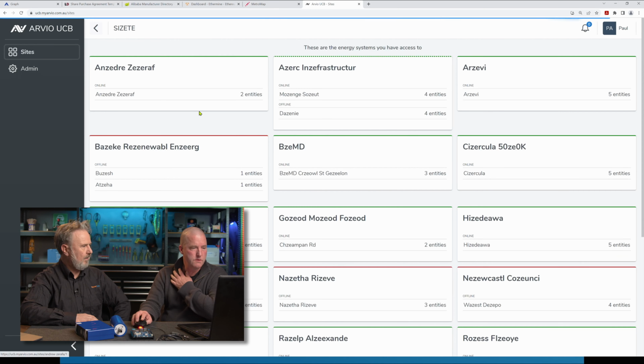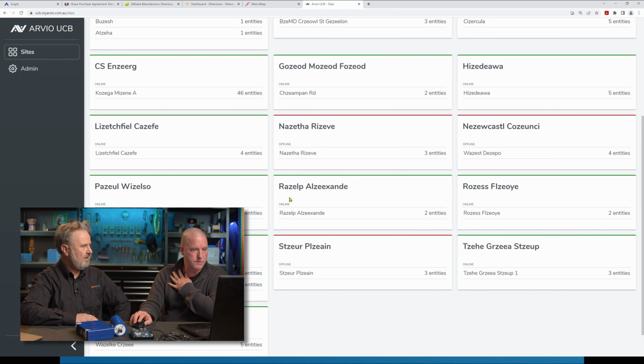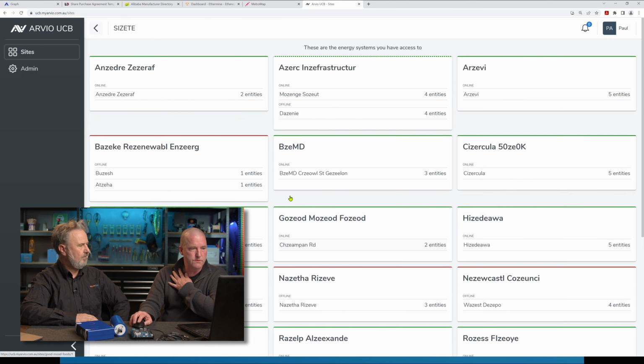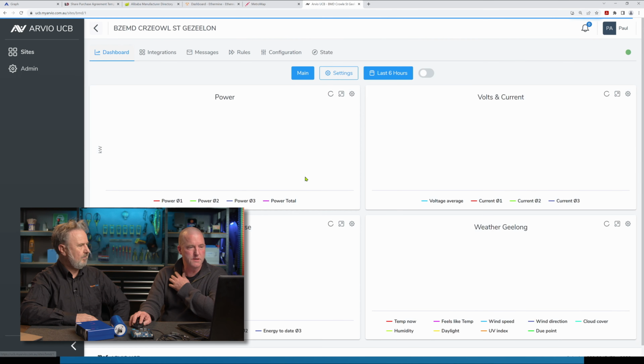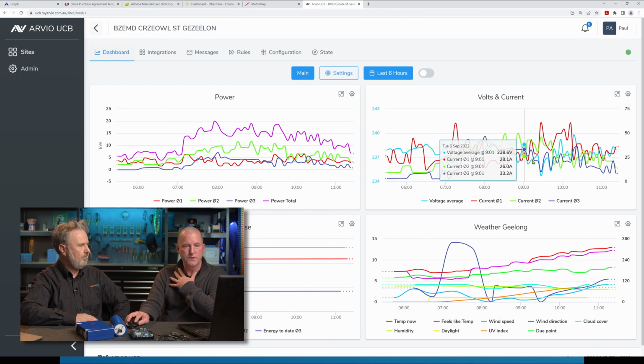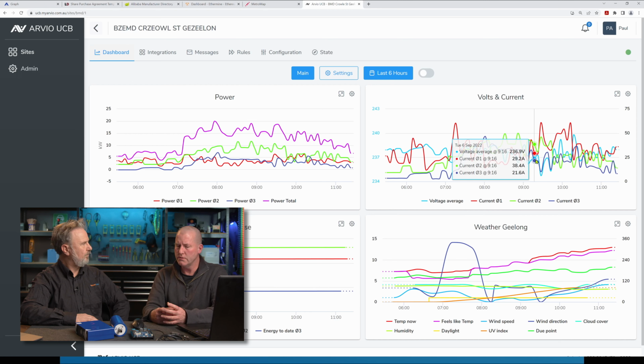We also did one the other day for a site where we wanted to measure a generator's performance over time. These are all encrypted at the moment. We put 3 current clamps around the 3 phases and fed it into a Wago, which is an electronics terminals brand, a really good brand from Germany. It had Modbus over RTU, over serial. So we took this cable and integrated it.